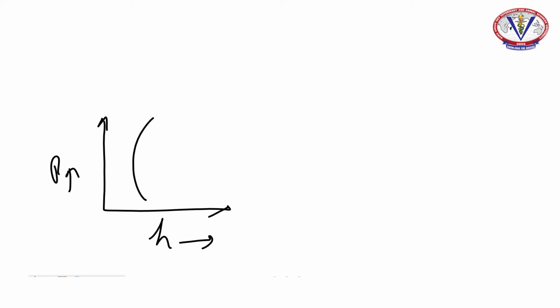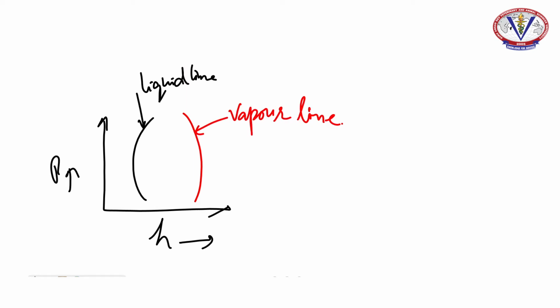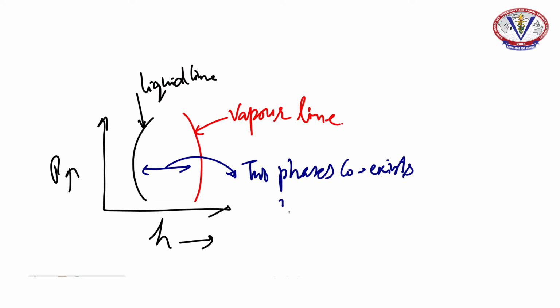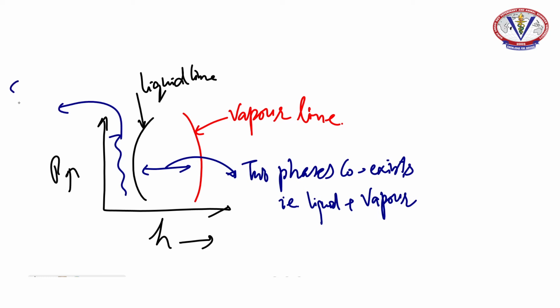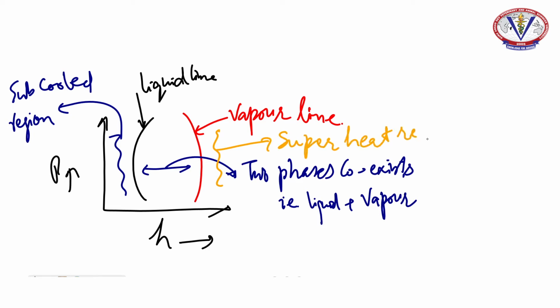On this P-h diagram we can see two curved lines. On the left hand side the line is known as the liquid line, whereas the curved line on the right hand side is known as the vapor line. It means if we follow the liquid line, the refrigerant will remain in liquid form, and as we move from left to right, from the liquid line towards the vapor line, the two phases, liquid and vapor, coexist. If we are nearer to the liquid line, that implies the refrigerant is in liquid form, and if we are closer to the vapor line, it means the refrigerant is in vapor form. Towards the left of the liquid line, the region is called the subcooled region, whereas the region to the right of the vapor line is known as the superheat region.